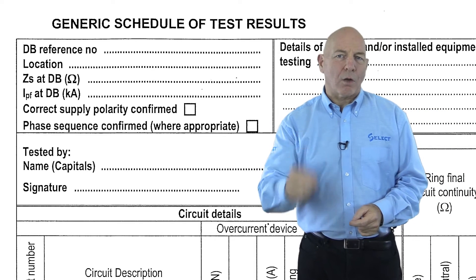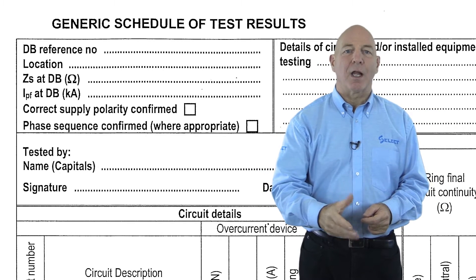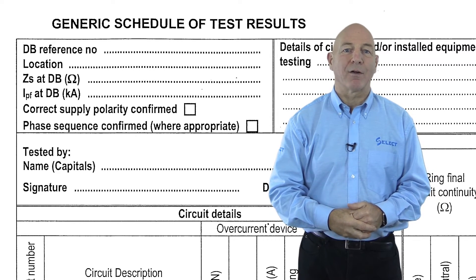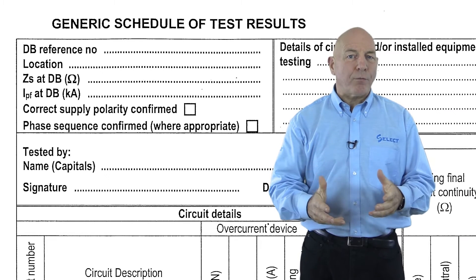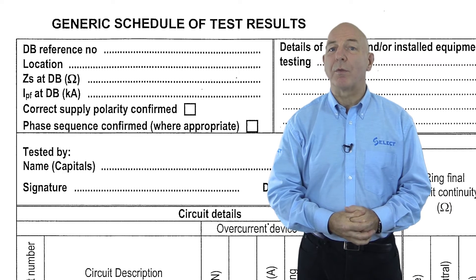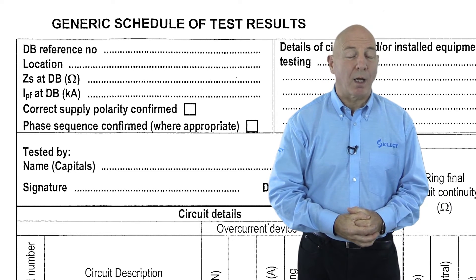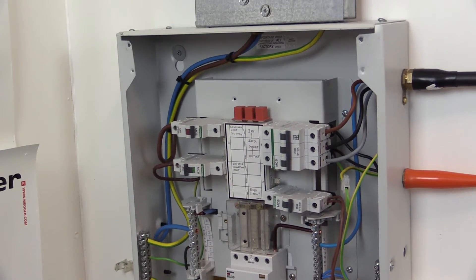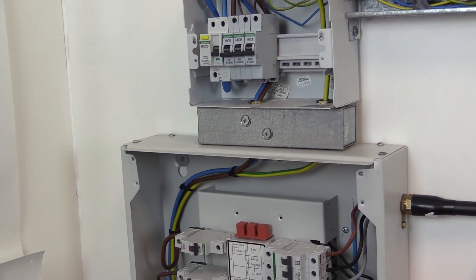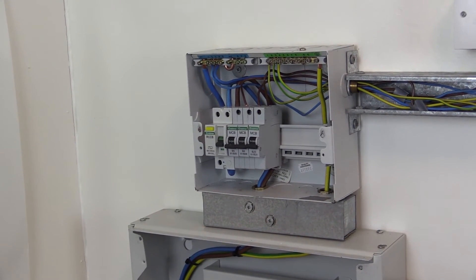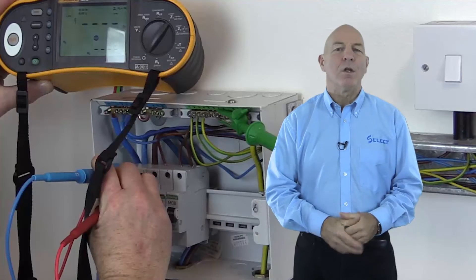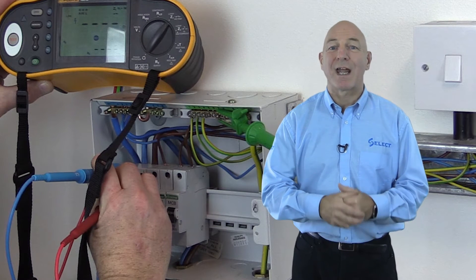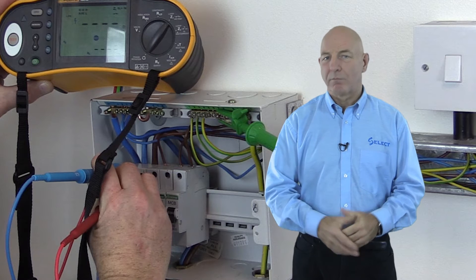To obtain the earth fault loop impedance external to the installation at the actual incoming supply to the building may require an additional test to be carried out at this position, but can often be obtained simply by inquiry with the building owner or the supply distributor. On small installations such as a dwelling, the situation is different, as the incoming supply to the building is normally located close to the main distribution board or consumer unit, so an earth fault loop impedance test carried out here can be regarded as the earth fault loop impedance external to the incoming supply, ZE.